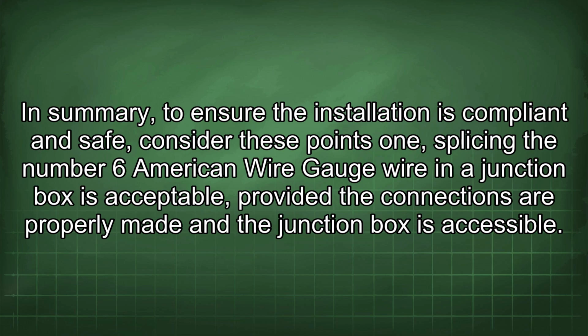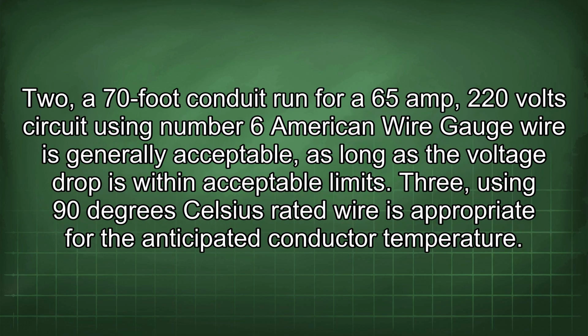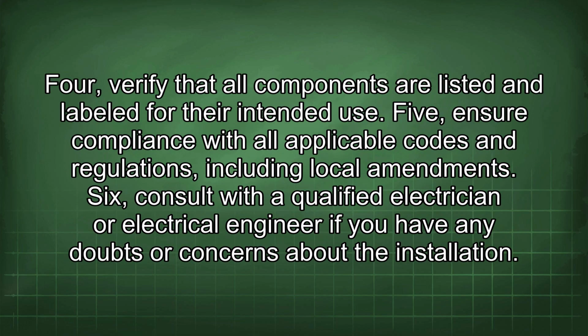1. Splicing the number 6 American wire gauge wire in a junction box is acceptable, provided the connections are properly made and the junction box is accessible. 2. A 70-foot conduit run for a 65 amp 220 volts circuit using number 6 American wire gauge wire is generally acceptable, as long as the voltage drop is within acceptable limits. 3. Using 90 degrees Celsius rated wire is appropriate for the anticipated conductor temperature. 4. Verify that all components are listed and labeled for their intended use.